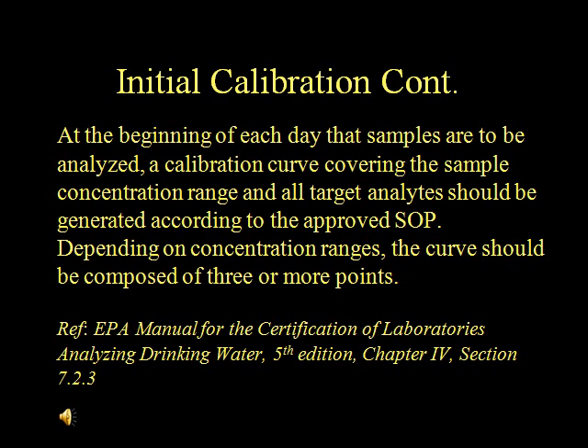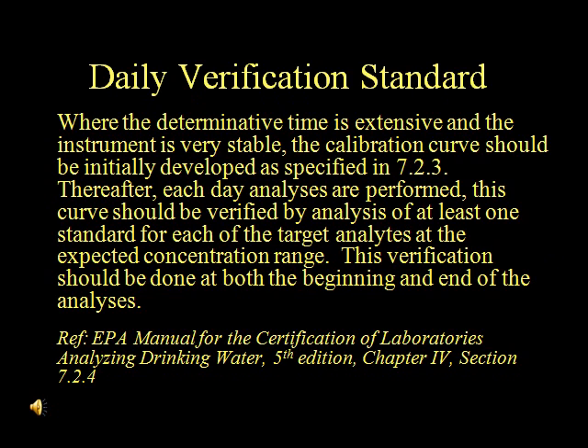According to the EPA Drinking Water Manual, if there are no calibration requirements in the method, the following are guidelines to be used. At the beginning of each day that samples are to be analyzed, a calibration curve covering the sample concentration range and all target analytes should be generated according to the approved SOP. Depending on concentration ranges, the curve should be composed of 3 or more points. In addition, the EPA Drinking Water Manual goes on to state that some calibrations are so time-consuming that an initial calibration is impractical on a daily basis. Once an initial calibration is developed and where the determinative time is extensive, such as methods 508, 508.1, 515.1, 524.2, 525.2, etc., and the instrument is very stable, the laboratory may choose to perform a daily verification standard.